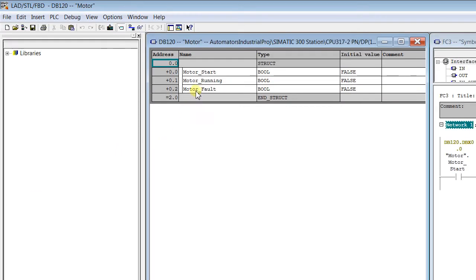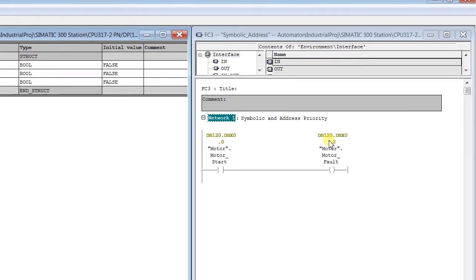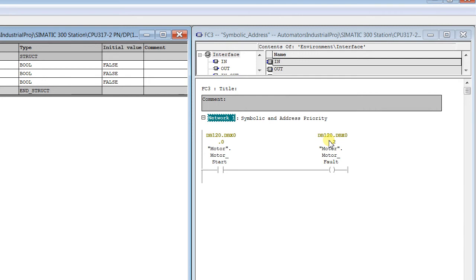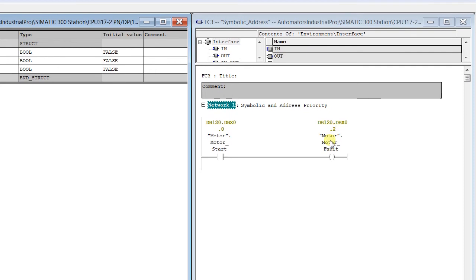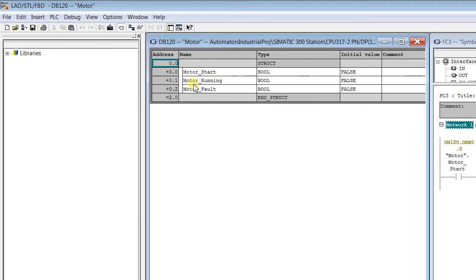I shuffled Motor Fault to address 0.2 and Motor Running to 0.1. The absolute address remains the same — it is not changing even though I changed the symbolic address. This is the drawback of absolute addressing: whatever symbol is changed, the address stays the same.